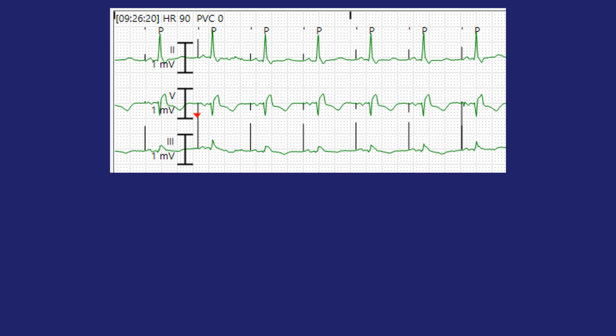And here we can see in this top image atrial pacing going on. And remember, of course, that on telemetry, the telemetry system has something called pacemaker mode that tells the telemetry system, please draw big lines where you think you see small pacer spikes. That's the reason that the color on the pacer spikes is different from the color of the rest of the EKG. It's because these black lines are in fact not recordings, but they are superimposed drawings that the telemetry system will show to help augment the tiny little green pacing spikes. In fact, you can kind of see one of them here on this particular channel. And again, the telemetry system is just trying to help us by augmenting that and making it bigger to make sure that we can see that pacing is occurring.